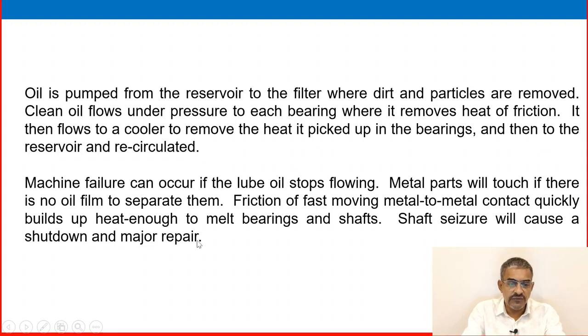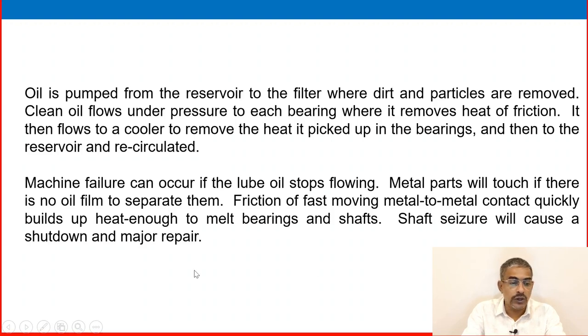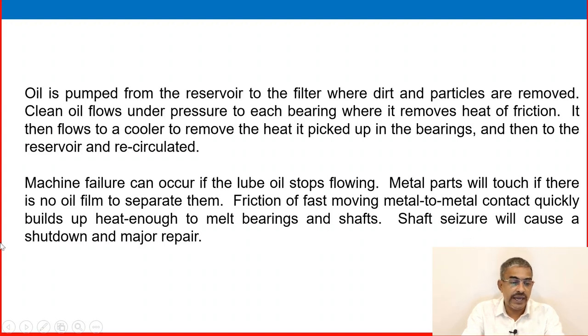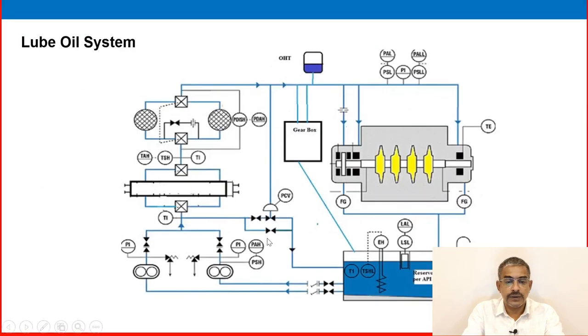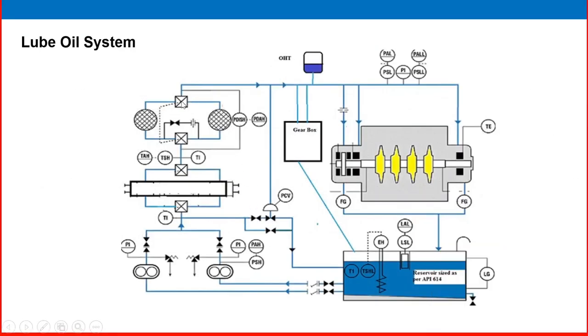Machine failure can occur if the lube oil stops flowing. Metal parts will touch if there is no oil film to separate them. Friction from fast-moving metal-to-metal contact quickly builds up enough heat to melt bearings and the shaft, causing a shutdown and major repair. This is why the lube oil system is so critical.